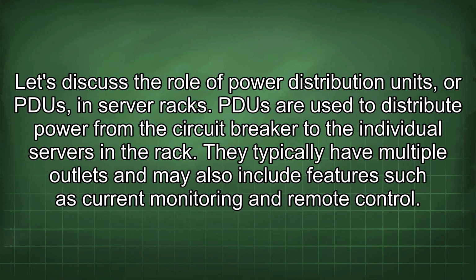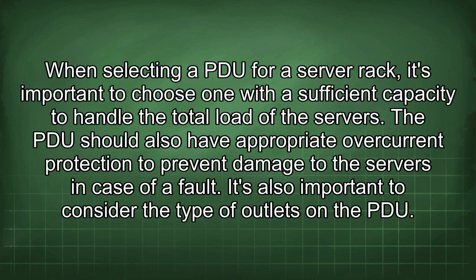Let's discuss the role of power distribution units, or PDUs, in server racks. PDUs are used to distribute power from the circuit breaker to the individual servers in the rack. They typically have multiple outlets and may also include features such as current monitoring and remote control. When selecting a PDU for a server rack, it's important to choose one with sufficient capacity to handle the total load of the servers. The PDU should also have appropriate overcurrent protection to prevent damage to the servers in case of a fault.